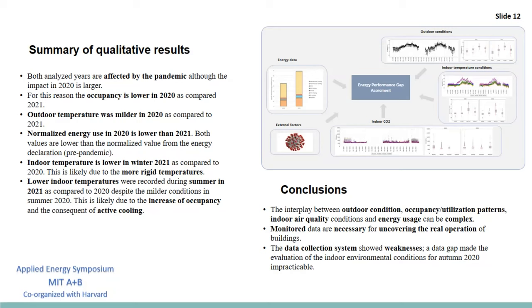Additionally, we can make some observations on the indoor air conditions. A first consideration is that the indoor temperature is lower in winter 2021 as compared to winter 2020. This is likely due to the more rigid temperatures during winter 2021. And the second consideration is that in summer 2021, lower indoor temperatures were recorded as compared to 2020, despite the milder conditions in summer 2020. And this is likely due to the increased occupancy and the consequent use of active cooling. And this shows that by linking energy along with indoor and outdoor conditions, we get a better picture of how the building is operating and the quality of the indoor air delivered and the corresponding energy use required.